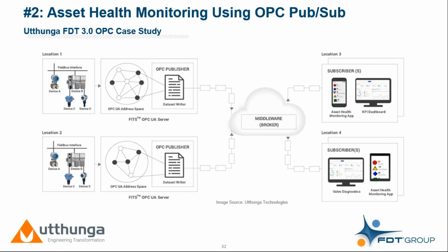With the client-server architecture, the client and server must maintain sessions, which consumes resources. So when you try to scale this application, you'll have problems managing each session and connection and handling the data. With the OPC PubSub mechanism, the publisher will not be aware of the subscriber, and the subscriber will not be aware of the publisher.